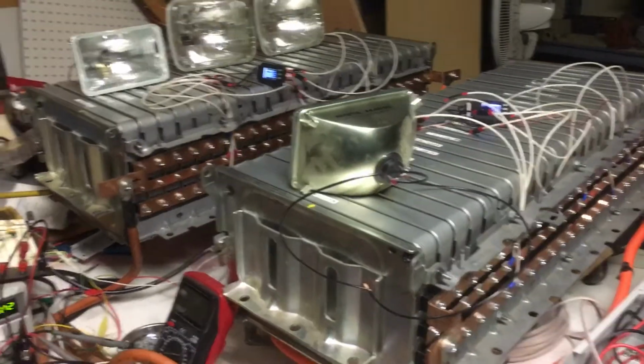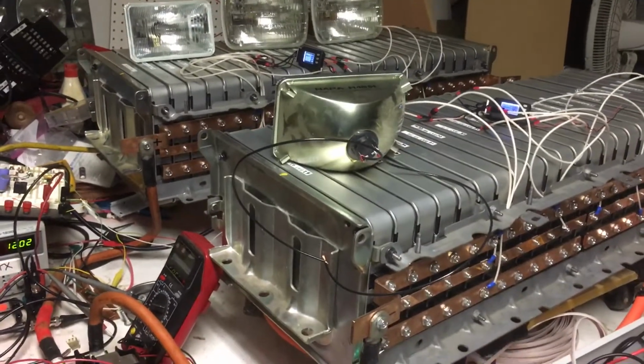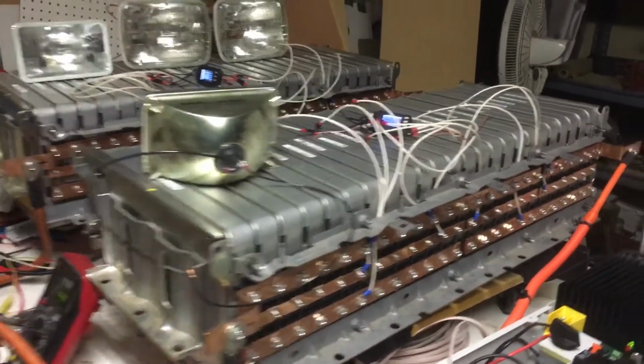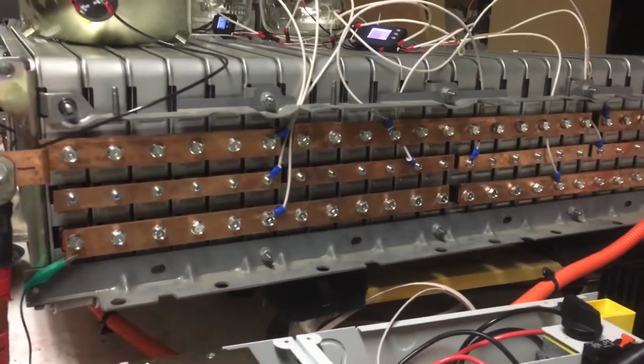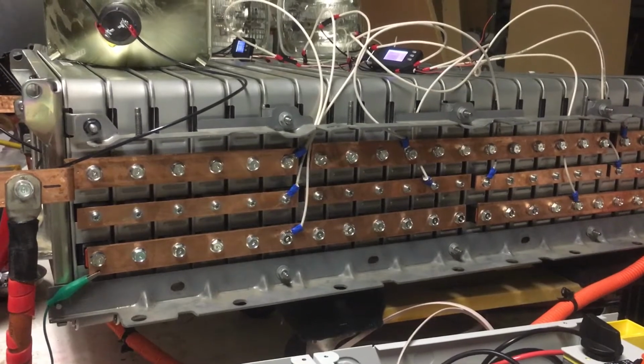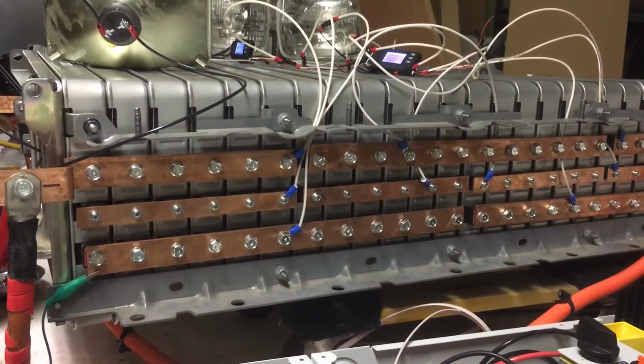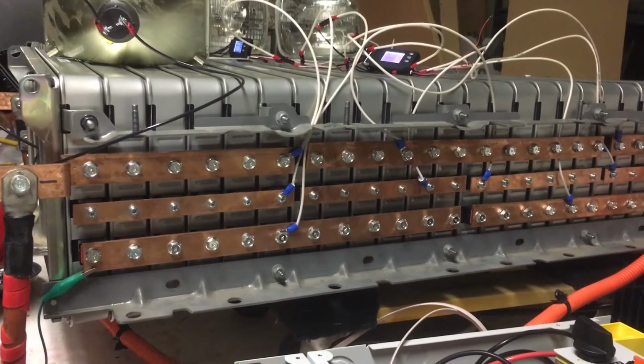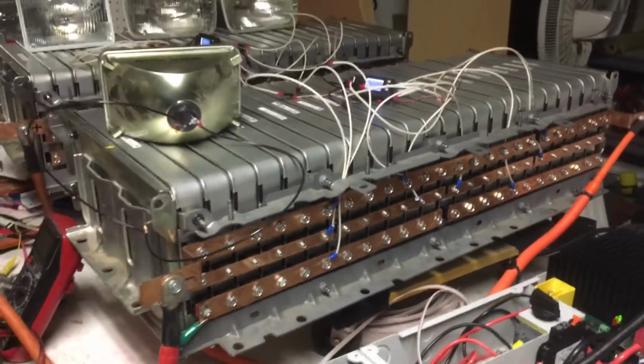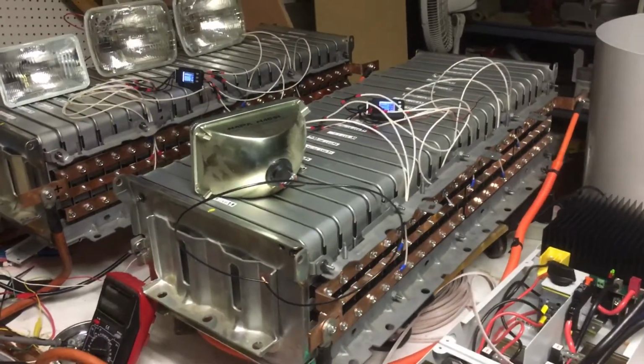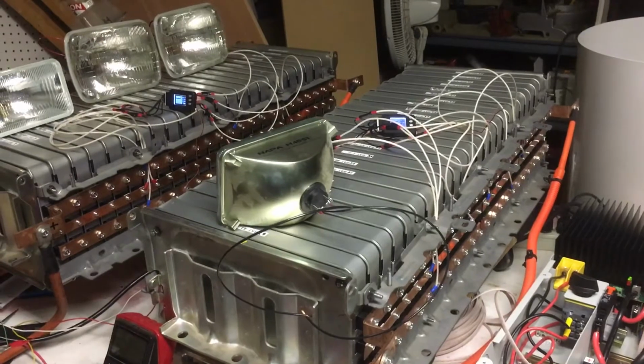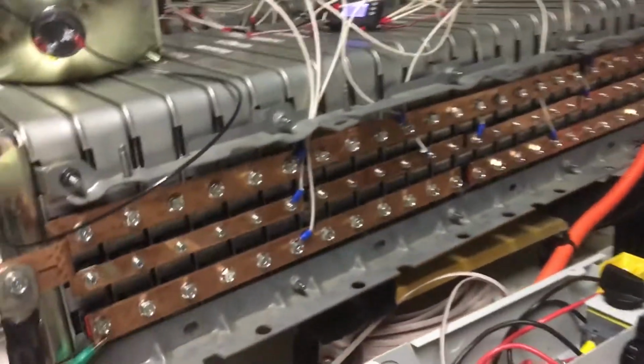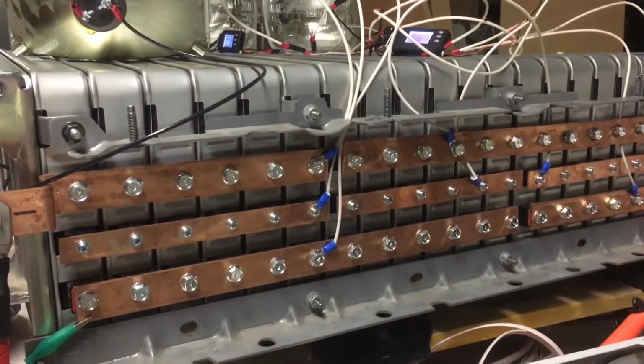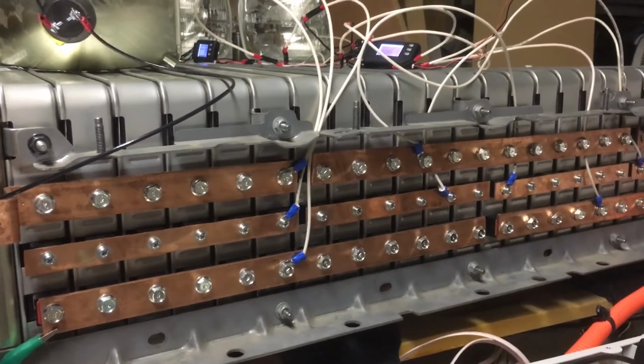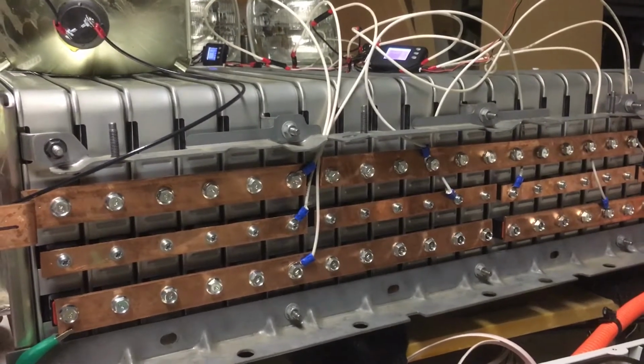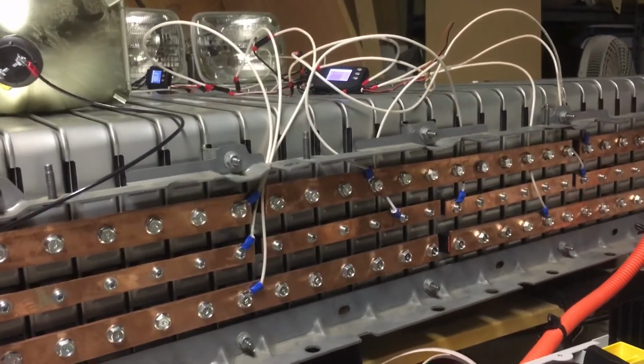You can see that's all been rewired. In the original configuration, it's about 360 volts with all the cells in series, but they've been rewired with these bus bars, so you have blocks of 6 modules in parallel. There are 8 of those in series, and with 2 cells in series in each module, you get 16 cells in series. That's why you have these center tap bars in the middle. Those are much thinner because they don't have to carry any current other than tying the cell voltages together and connecting to the BMS taps.